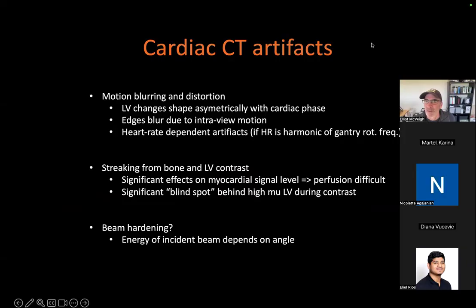So we have a few things we have to get over technically in terms of trying to measure something that's moving in a patient that's breathing, with dynamic contrast because we're injecting contrast. And so we have a few sources of image artifacts that as engineers we've got to try and get rid of. Basically, we do get intraview motion.